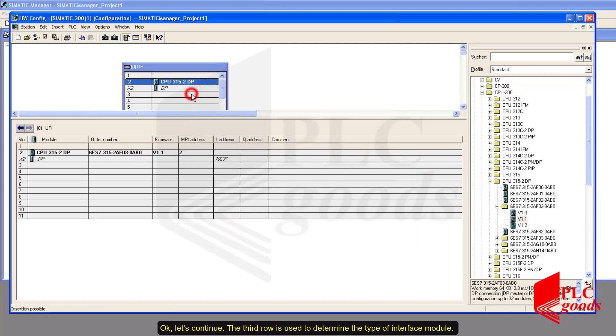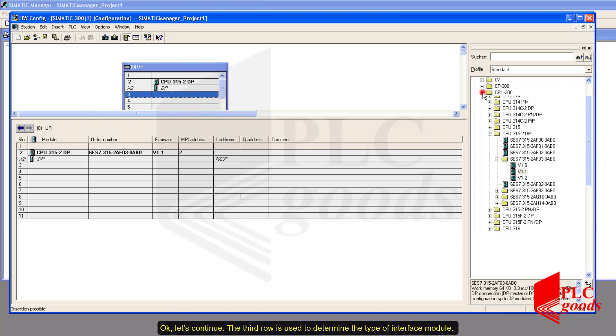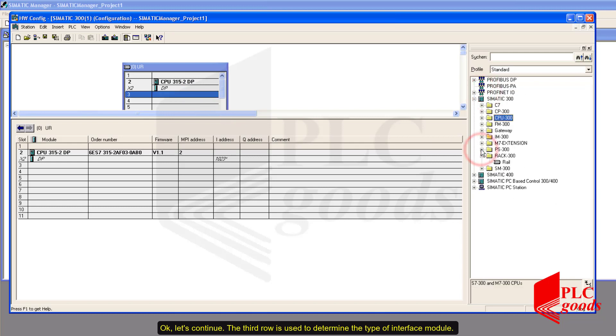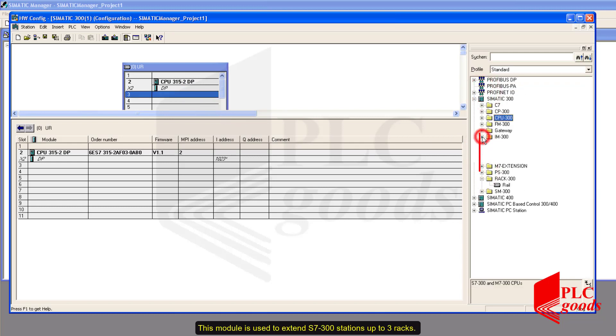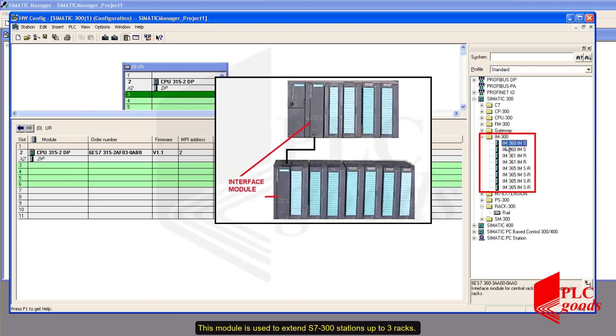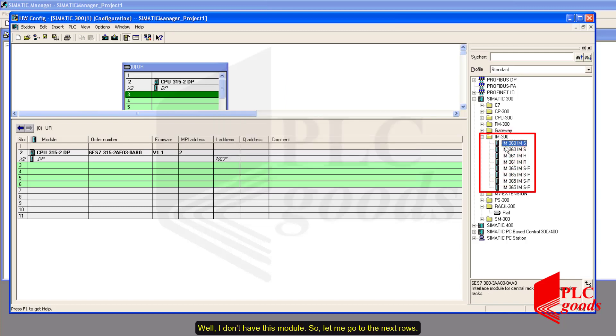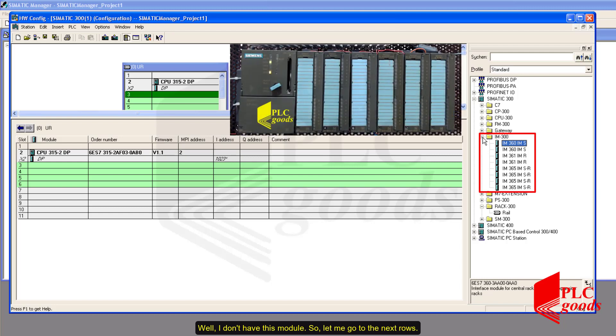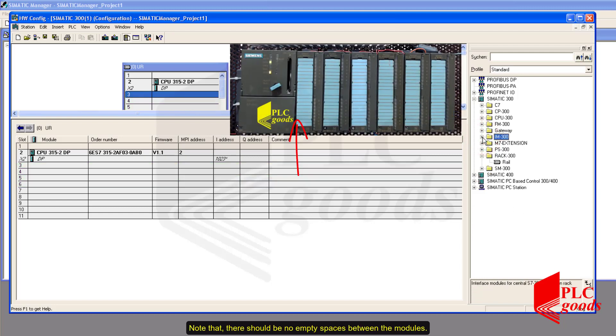The third row is used to determine the type of interface module. This module is used to extend S7-300 stations up to 3 racks. I don't have this module, so let me go to the next row. Note that there should be no empty spaces between the modules.